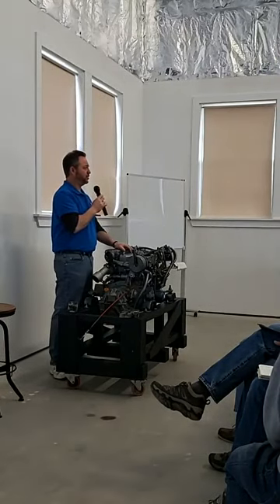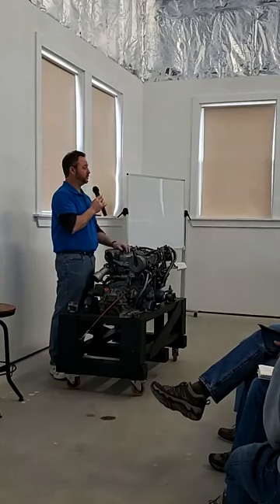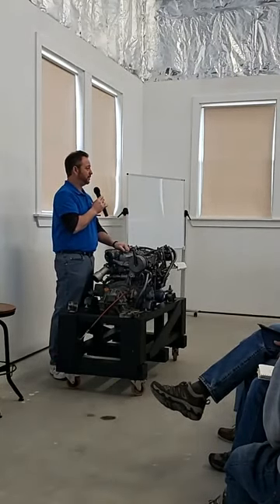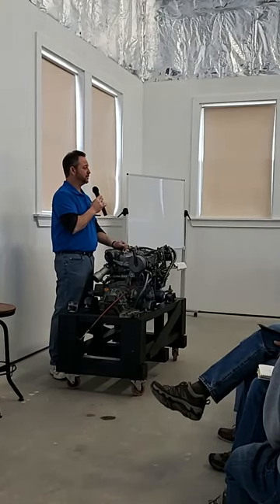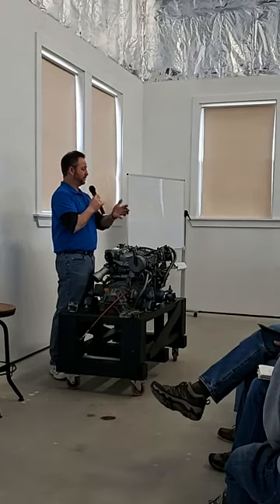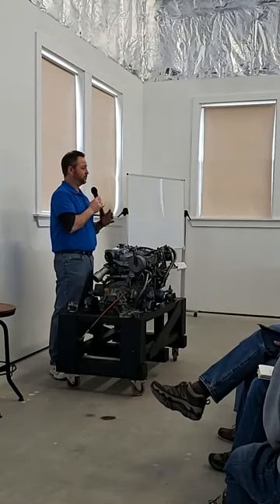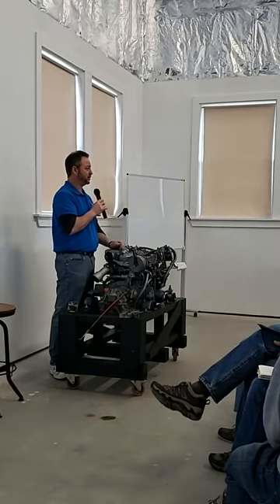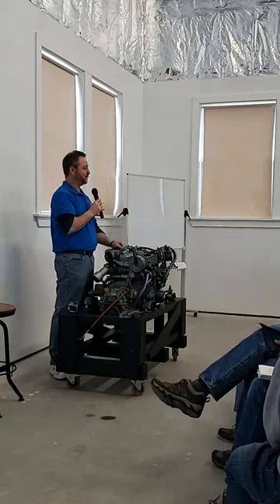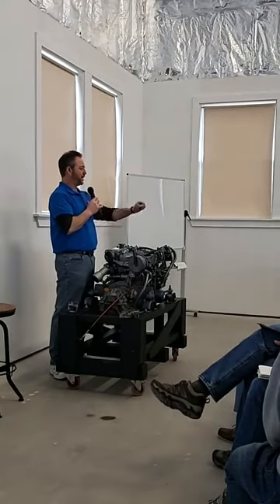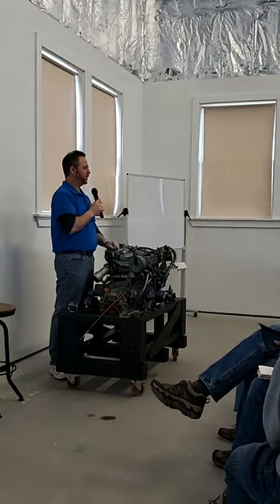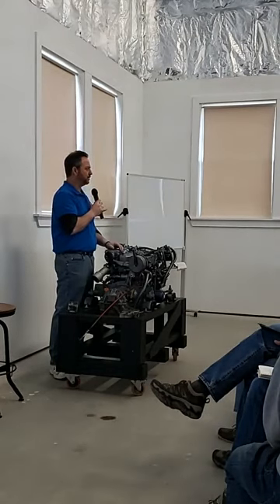Such a small tank. I mean, if you were worried about it, you could just pump it all out and put fresh fuel in. It's only 18 gallons, so you use it for the season. Most people only burn about half a tank throughout the season, and then just pump the rest of it out. As you're pumping it out, take a good sample off the bottom to see if there's any debris on the bottom of the tank, and put it into a clear bottle or something so you can see if there's any sediment.